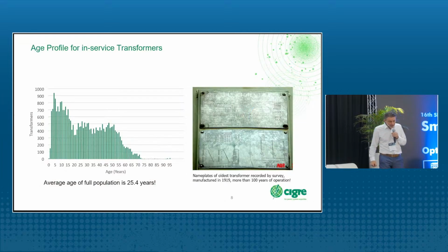So what you can see here is the age profile first of the in-service transformers, the transformers which are still working. We can see here that we have a considerable amount of data up to 60, 70 years age of transformers. The average age of the fleet is 25 years. But the oldest transformer we have in our database, that is the nameplate of the transformer. The nameplate is difficult to read, but this transformer was manufactured in 1919. So it has more than 100 years of operation, and it's still operating. And it's operating in North America, so they can be proud to have the oldest transformer in the grid.